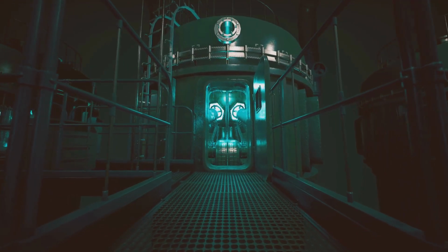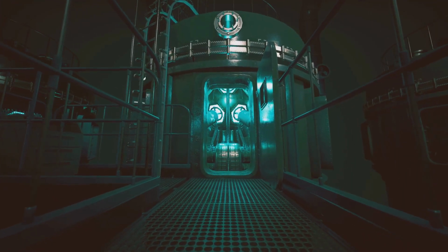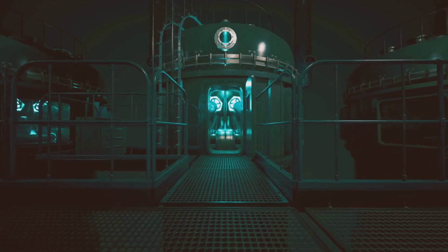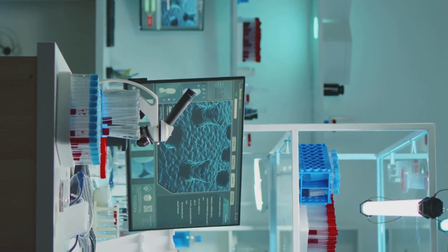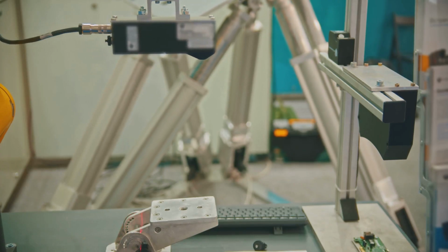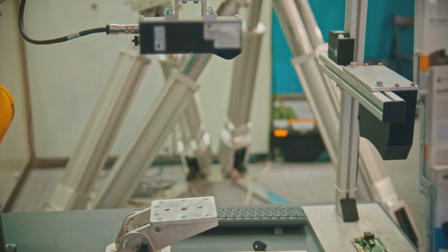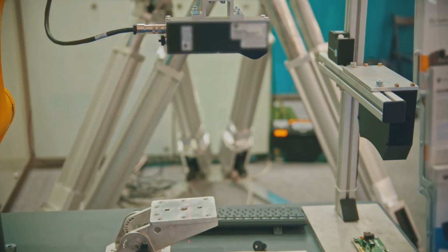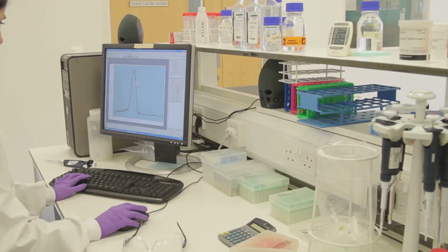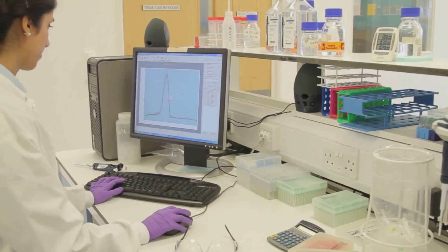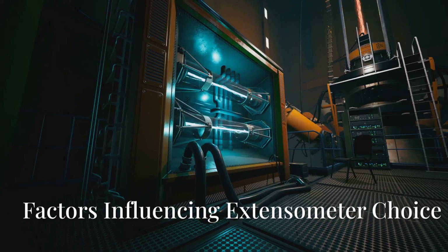The latest generation of non-contact extensometers, such as the laserXtens from Zwick, eliminate this source of error by using the unique structure of a specimen surface as a fingerprint to generate virtual measurement marks. These measurement positions are illuminated with laser light and detected by a camera that is integrated into the testing system. This allows the measured strain to be converted into direct extension value.